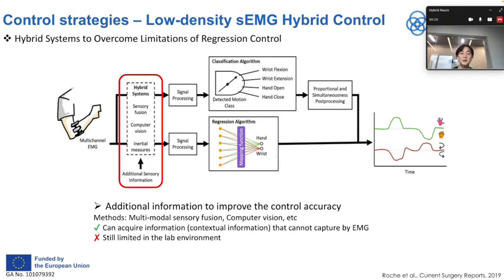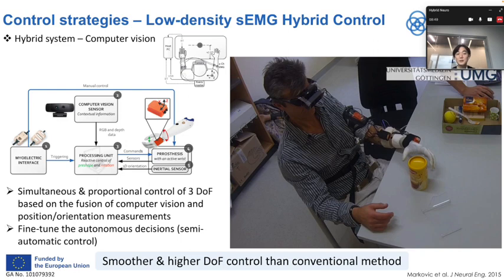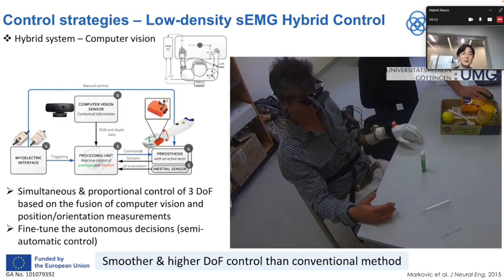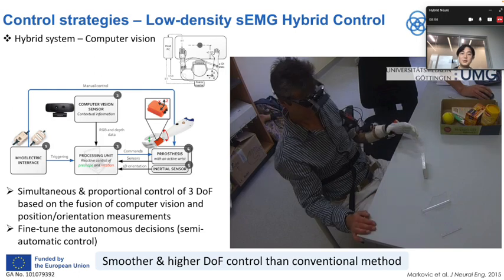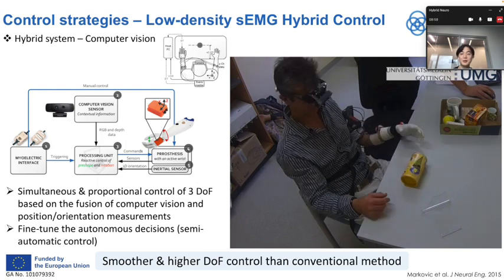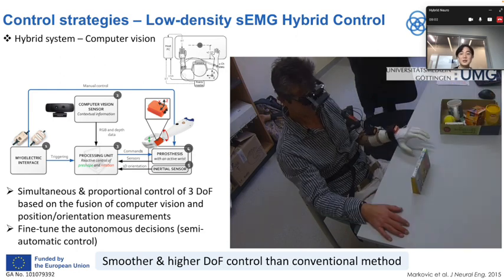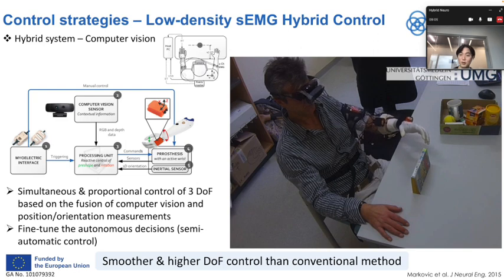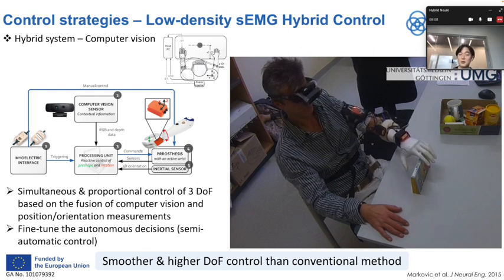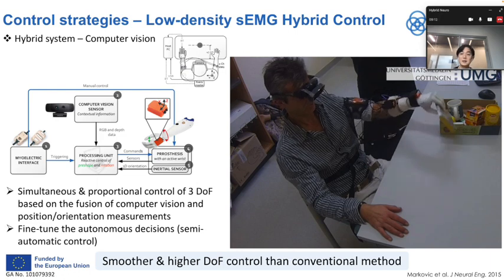There are further ways to overcome the limitations of regression control — for example, using multimodal sensory fusion or computer vision, which enables prosthesis control to acquire contextual information that cannot be captured by EMG alone. This demonstration shows how sensory fusion between EMG and computer vision can achieve smoother, higher degrees-of-freedom control than conventional methods. The user's input is an EMG channel for grasping or opening the hand, while computer vision controls the pronation or supination of the wrist and the hand gesture.